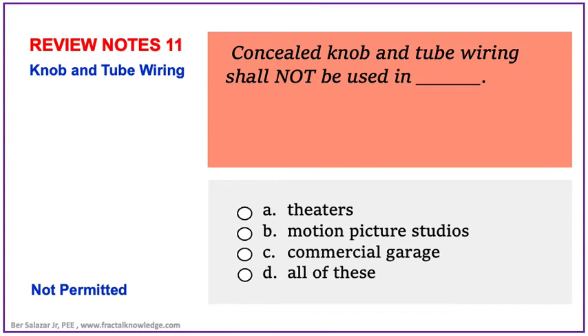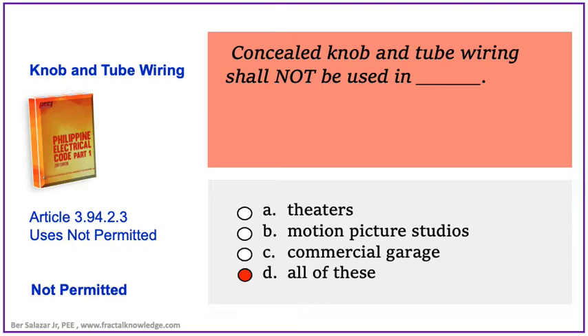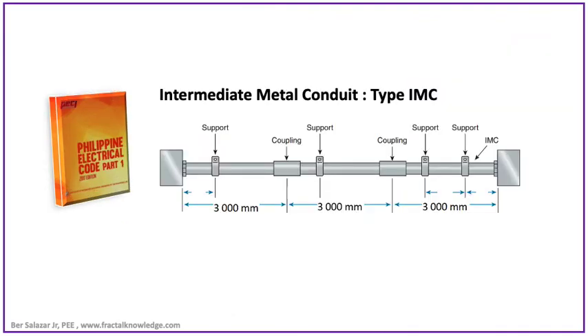Another possible problem asks about not-permitted usage. Concealed knob and tube wiring shall not be used in theaters, motion picture studios, commercial garages, or all of these. The correct answer can be found in PEC 2017, section 3.94.2.3 Uses Not Permitted, page 273. The answer is letter D: all of the mentioned places. Knob and tube wiring shall not be used there. Those are all the questions for concealed knob and tube wiring.